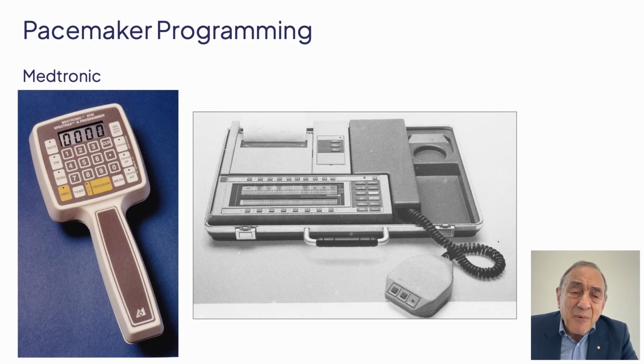These programmers had cassettes. For every different model, there was a specific cassette placed in the side of the programmer. The only issue was that I would be called in always on a Saturday night to the emergency room. I'd come in with the programmer and reprogram the patient, only to find that someone had that cassette in their pocket, meaning a very long evening in the emergency room.